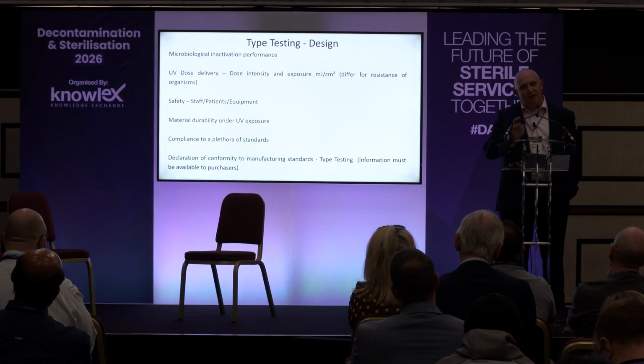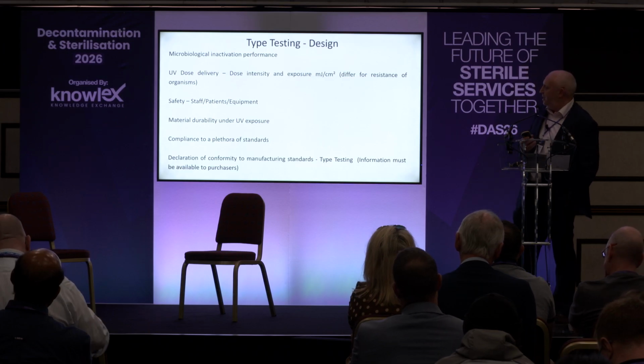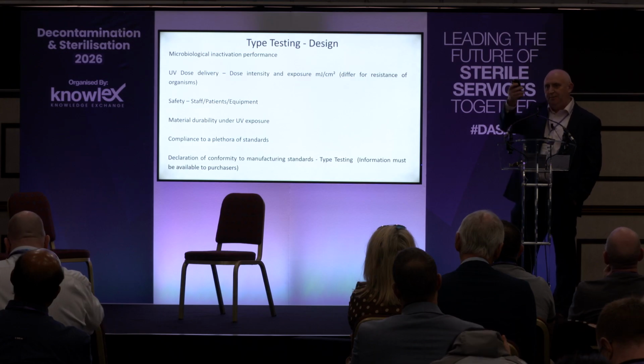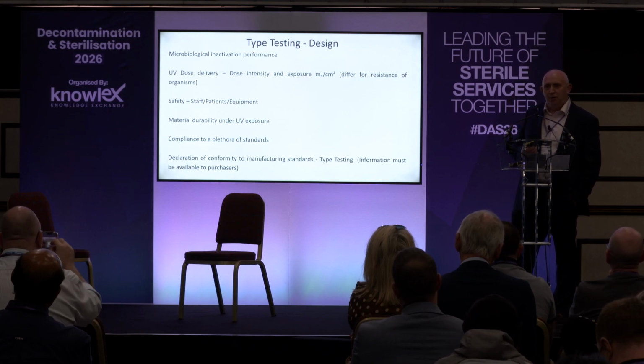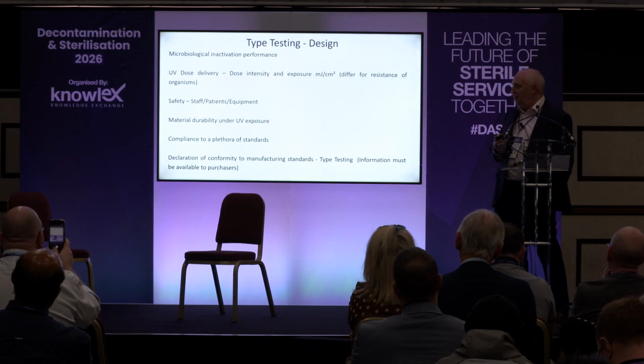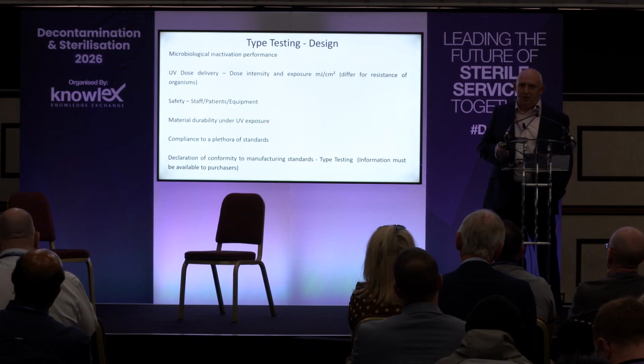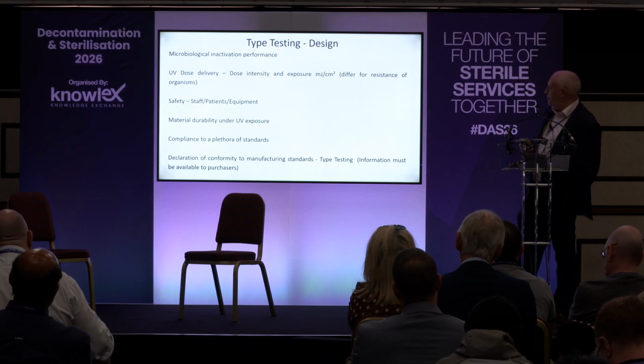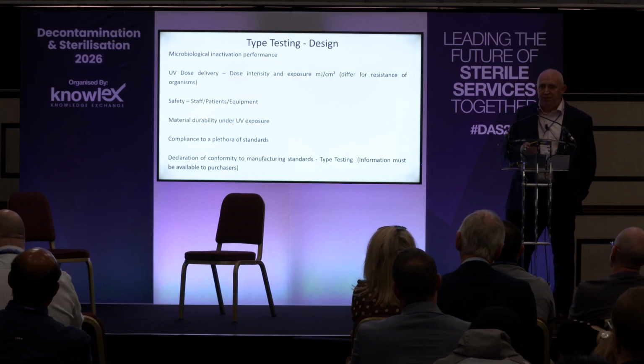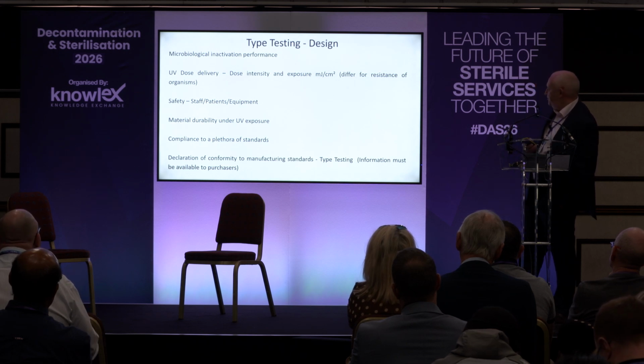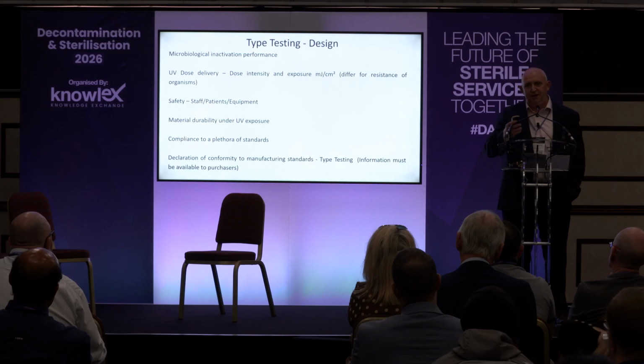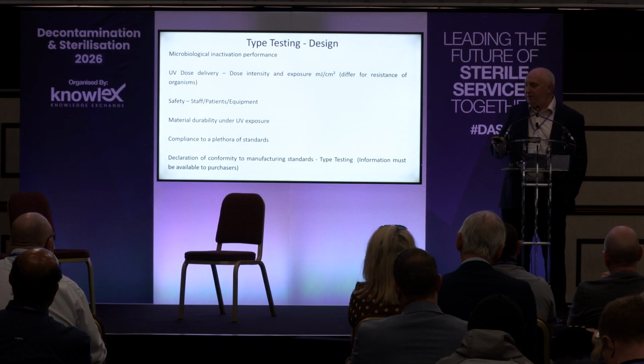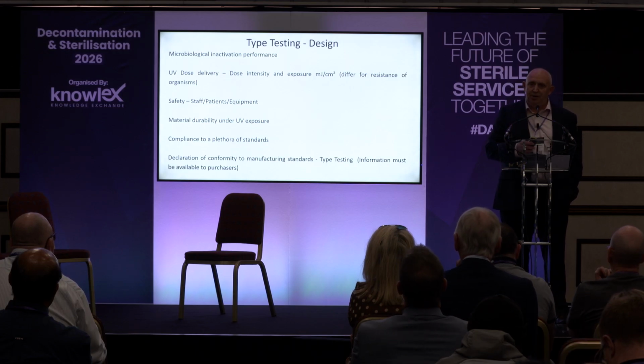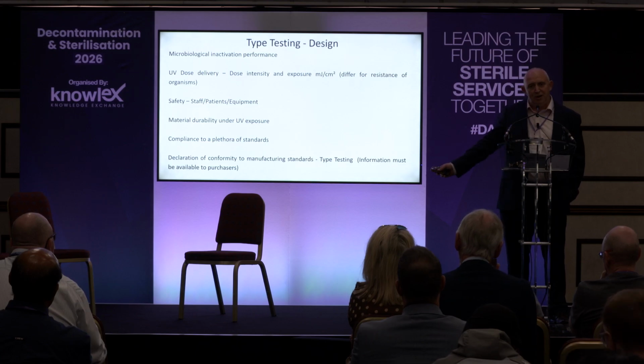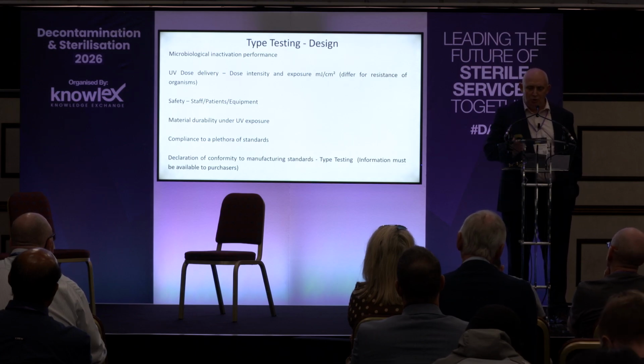Material durability. We're coming back to common themes here, yeah? If we have UV exposure on scope A supplied by Olympus, and I'm not picking on Olympus, but lo and behold, they're in the back of the room, yeah? There has to be compliance to a plethora of manufacturing standards. And there has to be a declaration of conformity to all those particular standards. Now, the type testing, in the event of an argument between a supplier and a trust, that information should be presented to back up the information provided, yeah? So the procurement department should build a statement into the procurement documents to state that fact.